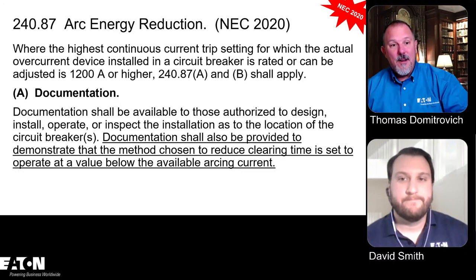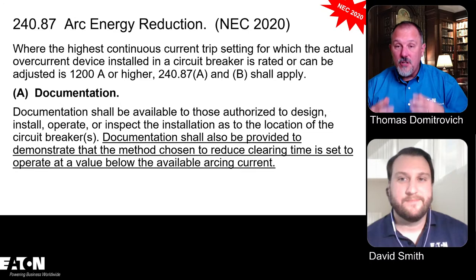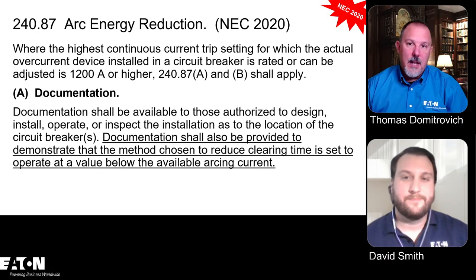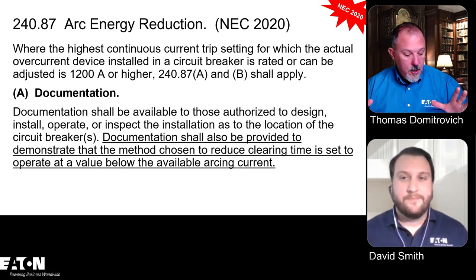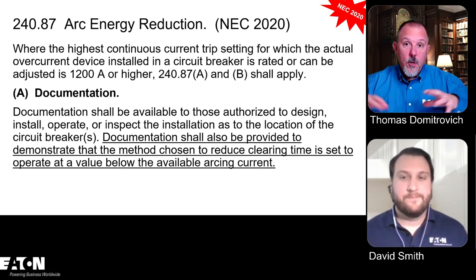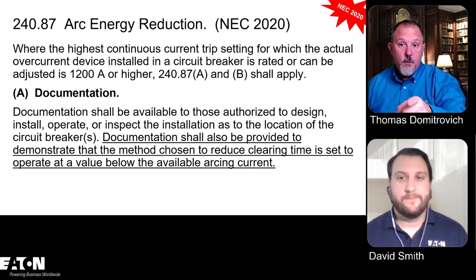And I agree with you, Robert. We probably should define available arcing current as well. And that would be a good public input, in my opinion, for both 70E and the National Electrical Code, because nowhere do we define that. And we're using it in 240.87 and in 240.67.